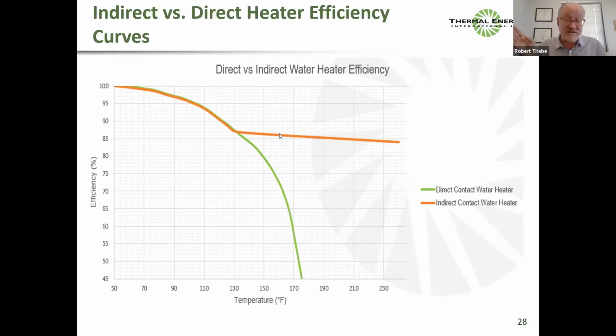Well, you cannot use these curves for a direct contact water heater, because in a direct contact water heater, your exhaust is 100% humid. And when your exhaust is 100% humid at 160 degrees, your efficiency is actually 72%. And it plummets because a direct contact heater is spraying water into the flue gas. So if you imagine, it'd be like going to a traditional boiler and cooling the water down by spraying it in the stack and then saying, now it's 160 degrees Fahrenheit, and so my boiler is more efficient.